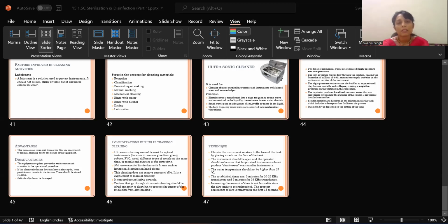Now, what have been the major concerns regarding the implementation of this scheme? Firstly, oversimplification. This scheme does not consider problems with reprocessing of complicated medical equipment that is often heat sensitive, or problems of inactivating certain types of infectious agents like corona. Particularly, a few medical devices in the critical category cannot be steam sterilized because they are heat sensitive. Additionally, sterilization using ethylene oxide can be too time consuming for routine use, such as with endoscopes and laparoscopes.